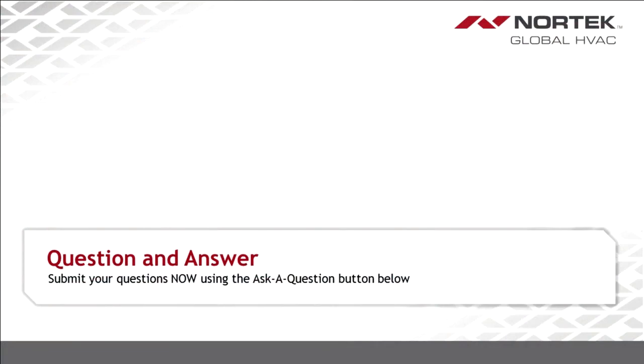Okay, sounds great. Greg, Wally is asking if Nortek requires a heat pump to turn off at a low temperature. As an example, if it were minus 10 degrees Fahrenheit outside, should we run the heat pump along with the backup heat strips, or just the heat strips alone? That's a really good question. So, do we require shutting the heat pump down and using the backup heat at any specified temperatures?